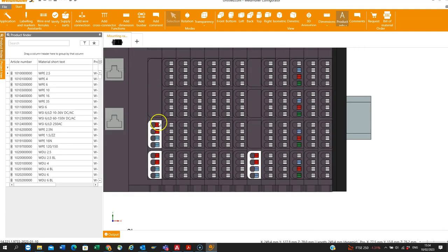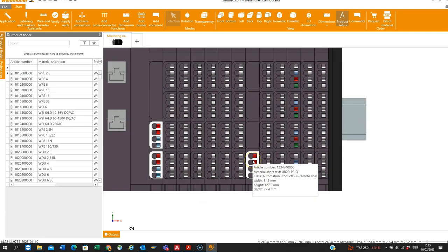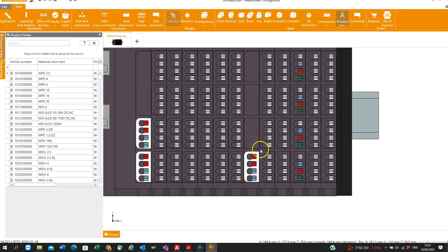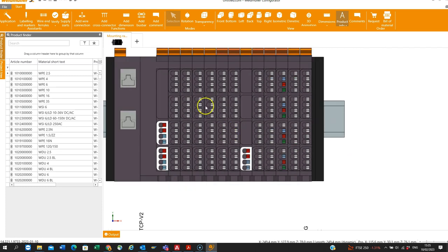So you notice that white pins are signal, the red pins are plus 24 volt, and the blue pins are 0 volt. So these two connectors on the left are in power and out power. So they're both inputs to the system. One's feeding input modules, one's feeding output modules. You can daisy chain across, so you can come out of the red top connector into the red bottom connector, if that's what you want to do. And then here, again on that particular card, you've got a signal, a blue, a red, and a green. So green being functional earth.